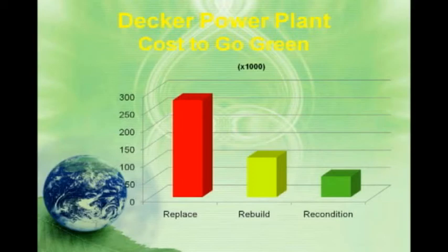What this really brings into play is, in looking at those systems and those motors that really were operating in an inefficient or an unreliable state, could we apply a reliability approach to these motors and actually recondition them? Those that needed to be rewound, but those that needed to be reconditioned, let's just clean them up. Let's align them. Let's remove the power circuit anomalies. Let's verify that inductively these things are balanced. Let's verify the insulation integrity is good.